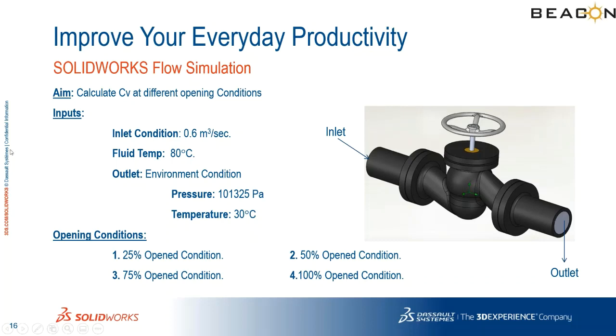In the first case study, I have a globe valve where one side is the inlet and the other is the outlet. My aim is to calculate the Cv at different opening conditions. Using SOLIDWORKS CAD configurations, I can make the handle go up and down to compute Cv at different openings. The inlet condition is a flow rate of 0.6 cubic meters per second at 80 degrees Celsius. The outlet is at environmental conditions at 30 degrees Celsius.